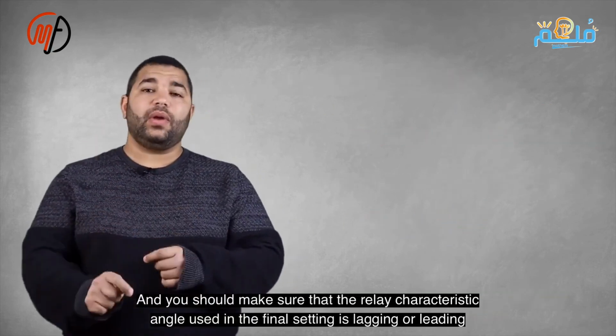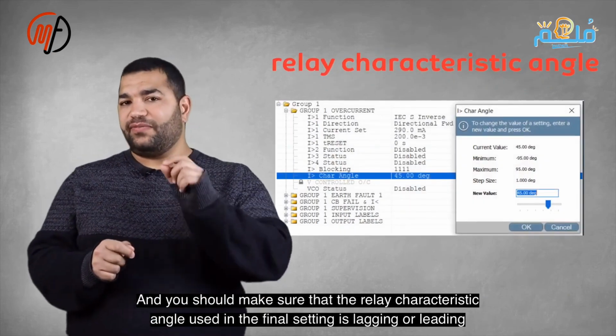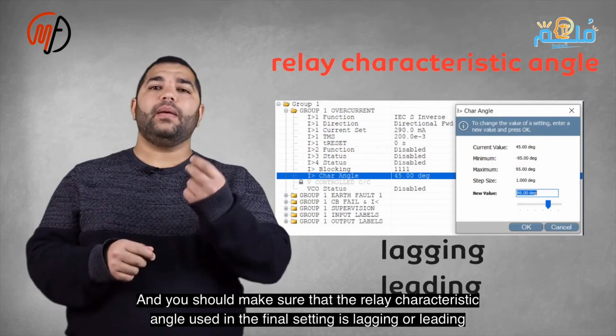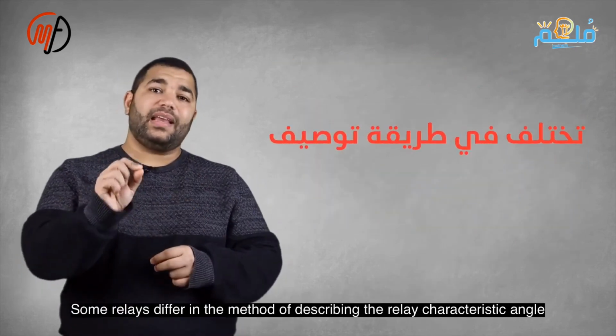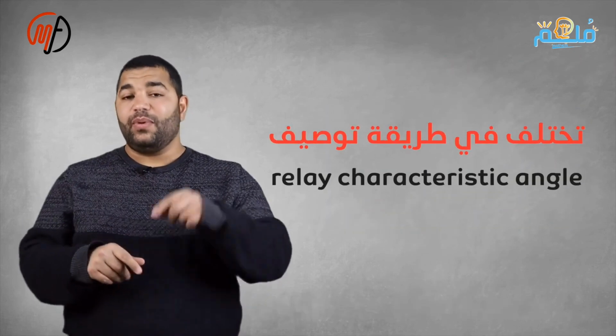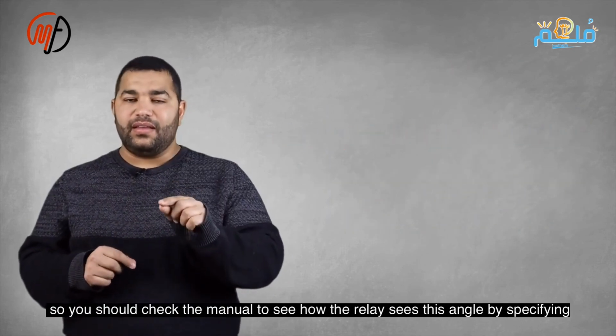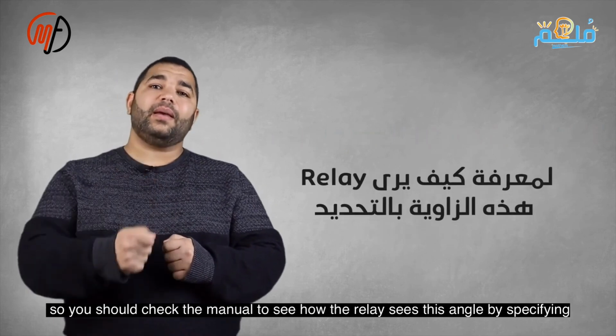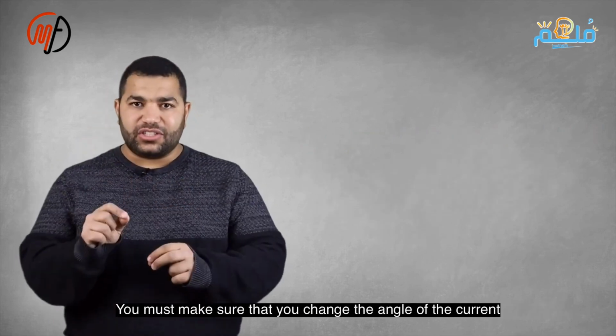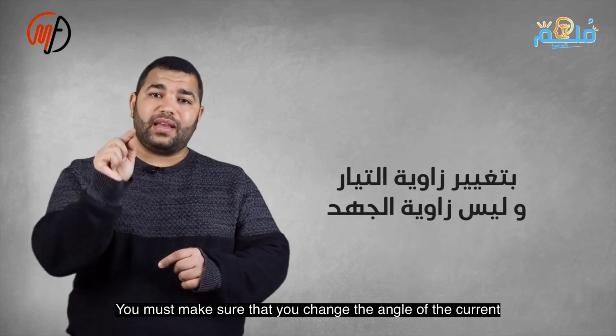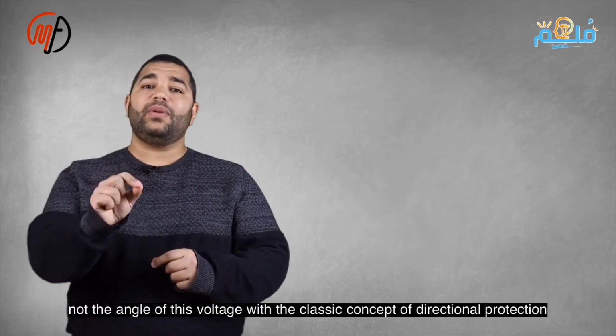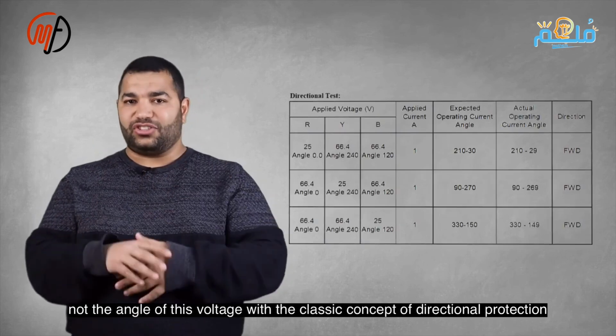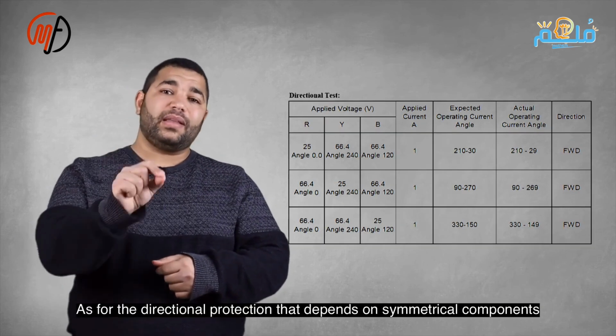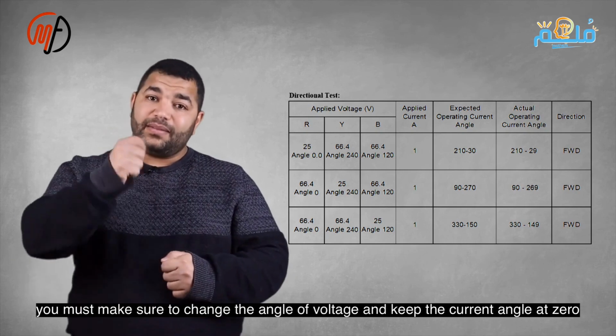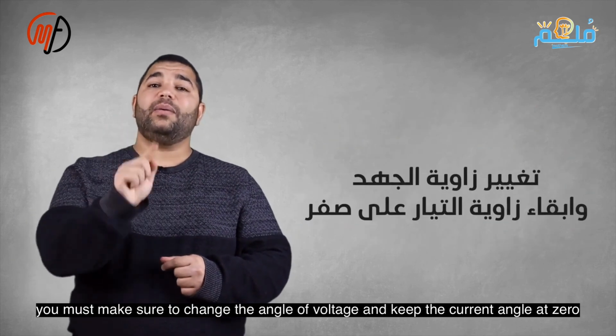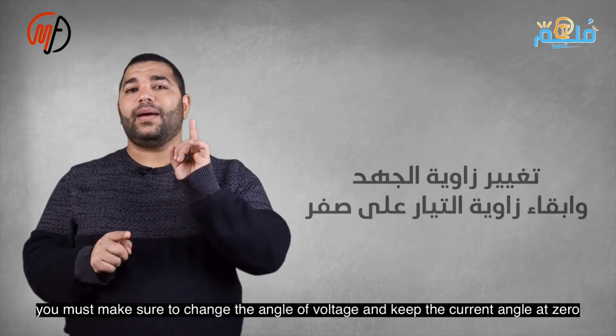You need to ensure whether the relay characteristic angle used in the final setting is lagging or leading. Some relays differ in how they describe the relay characteristic angle, so you should review the manual to understand how the relay perceives this angle specifically. You must also ensure that you are changing the current angle, not the voltage angle, as per the classic concept of directional protection.